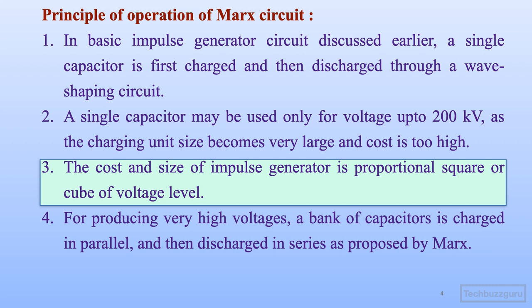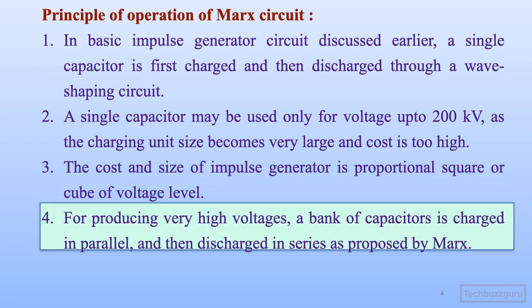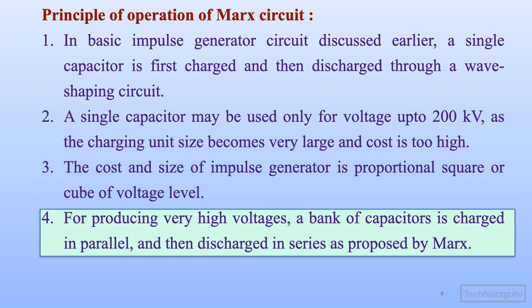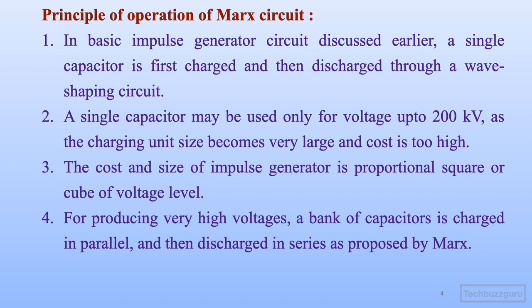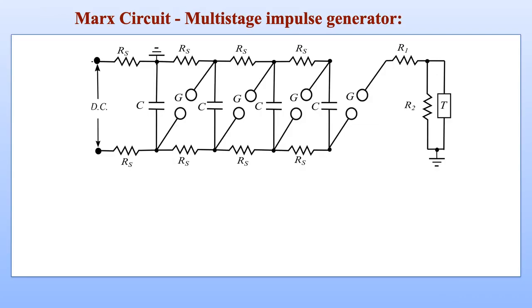The cost and size of the impulse generator is proportional to the square or cube of the voltage level. For producing very high voltages, a bank of capacitors is charged in parallel and then discharged in series, as proposed by the Marx circuit. This is the basic principle of operation of the Marx circuit.